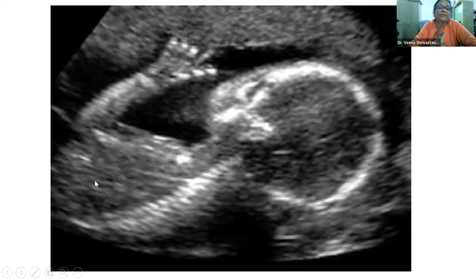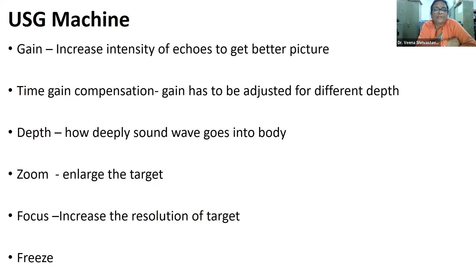Now I will be telling you something about the machine. To get a good picture on the monitor, you have to manipulate certain buttons which are present on the keyboard. First is gain. By manipulating the gain button, you increase the intensity of echoes, and you get a better picture. Another is time gain compensation, which adjusts the gain according to the depth of the field. Third one is depth, and it will decide how deeply the sound wave should go in the body. Fourth one is zoom. By manipulating this button, you can enlarge the target. And another is focus, which increases the resolution of the target. And last one is freeze. You have to press the freeze button whenever you want to measure anything.